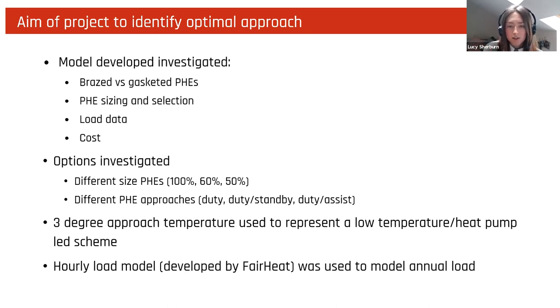The model used a 3-degree approach temperature across the plate heat exchanger. This was used to represent a low temperature scheme or heat pump led scheme. I also used load data from a theoretical hourly load model, which was developed by FairHeat. This load model had 4 different scheme sizes, going from 100 units to 1,000 units. So scheme size was also investigated within this, but for the purposes of this presentation, I'm just going to look at the 250 unit size scheme.